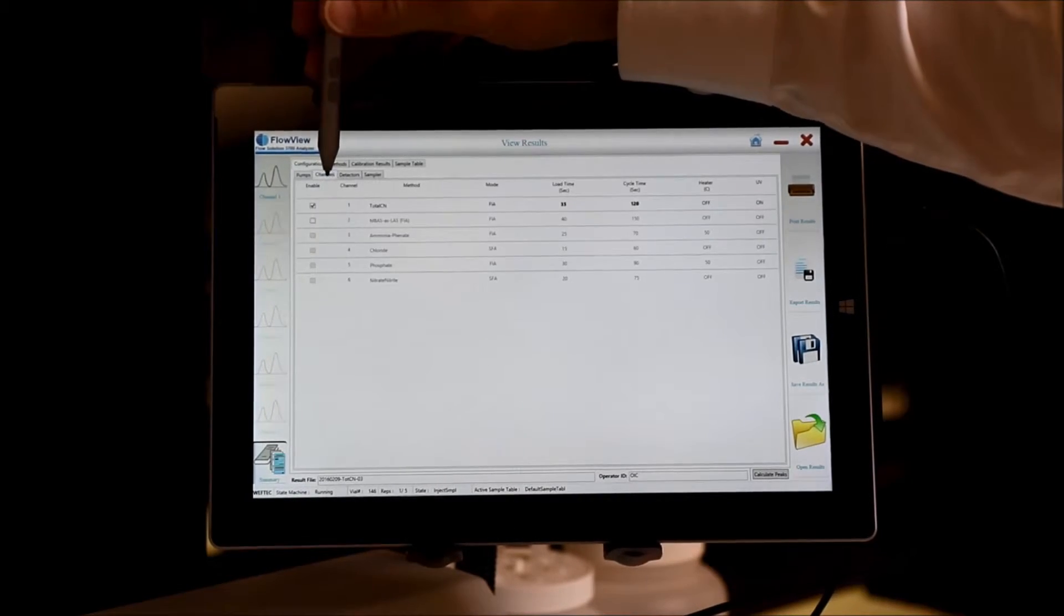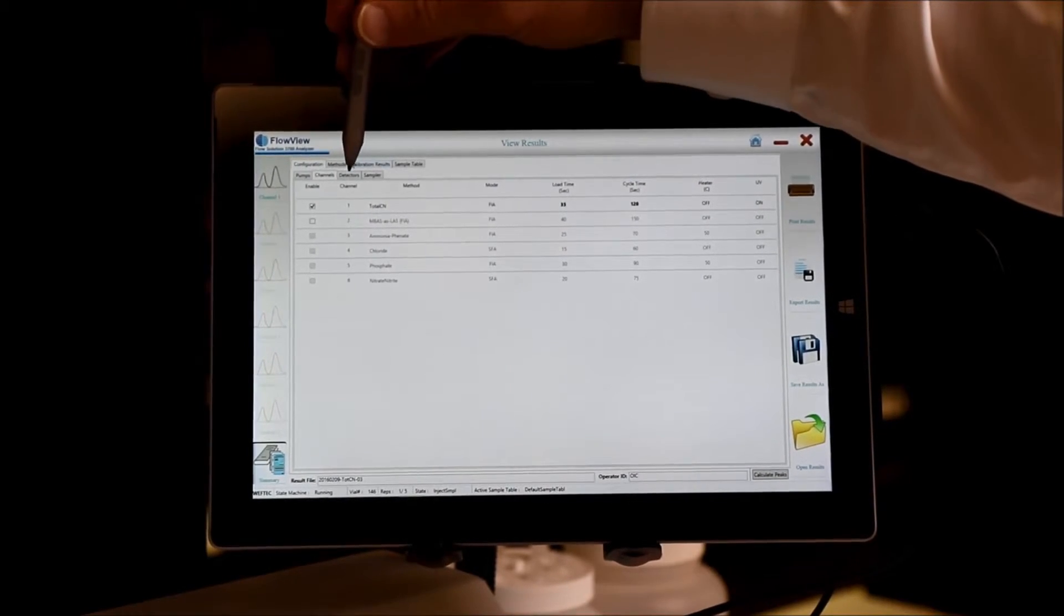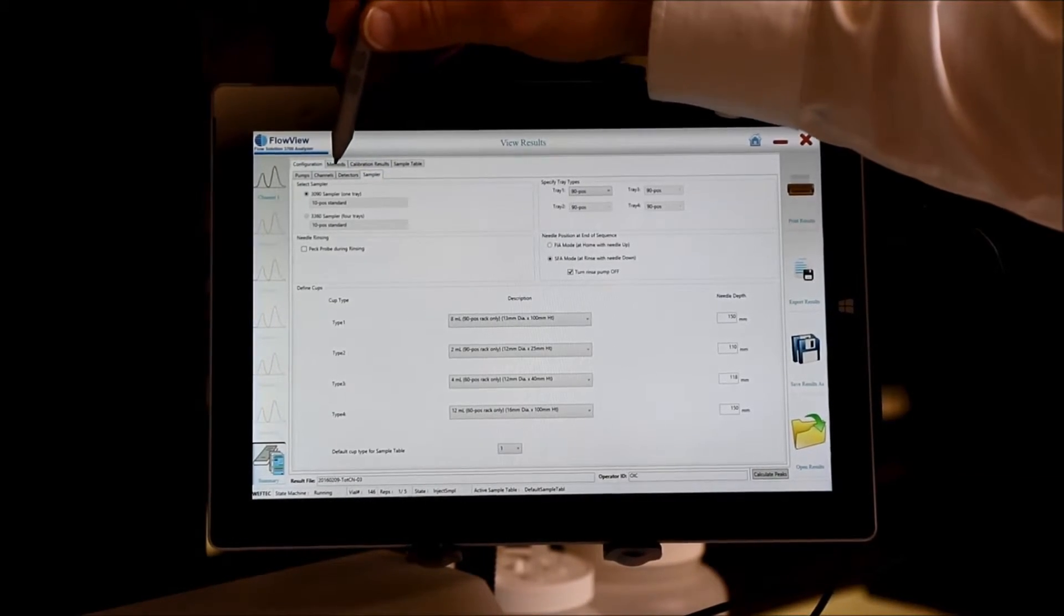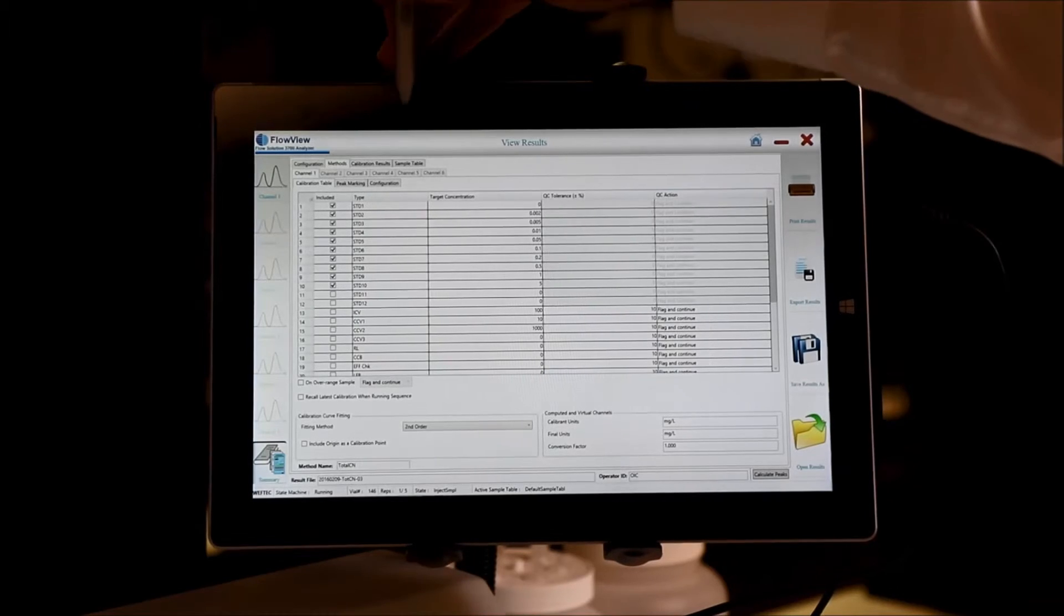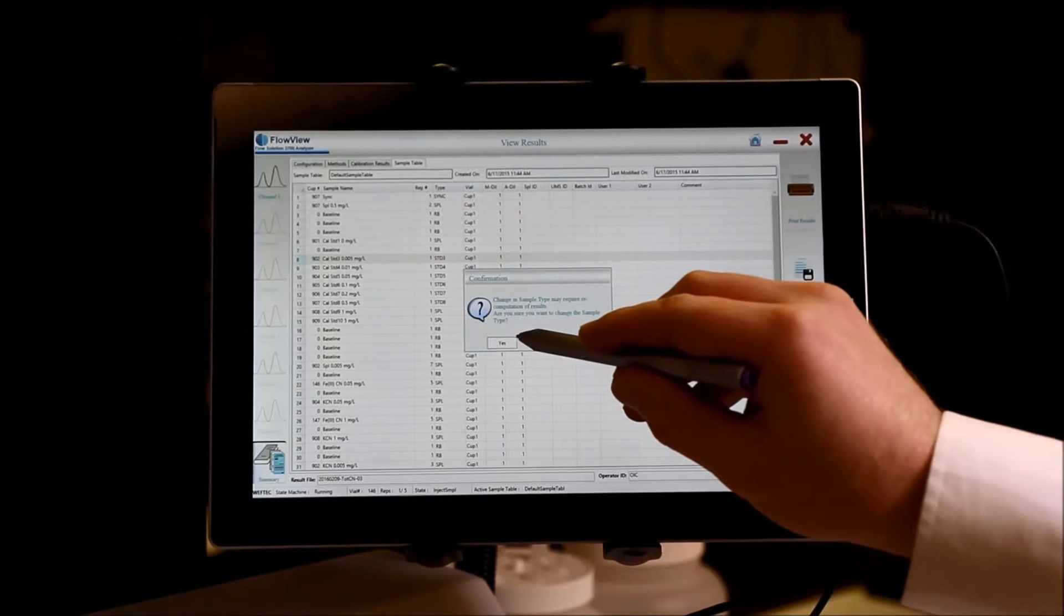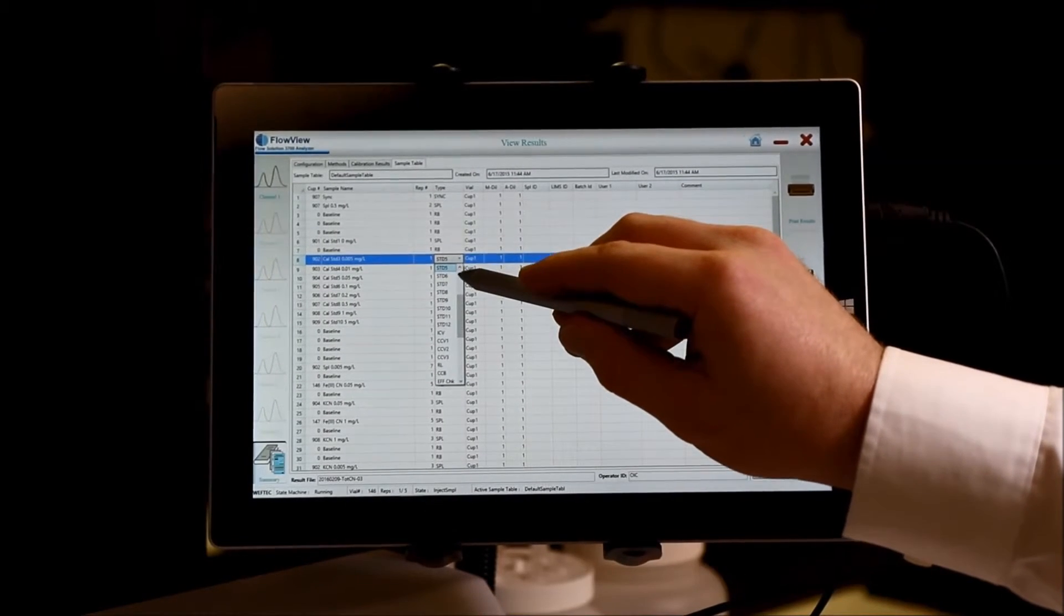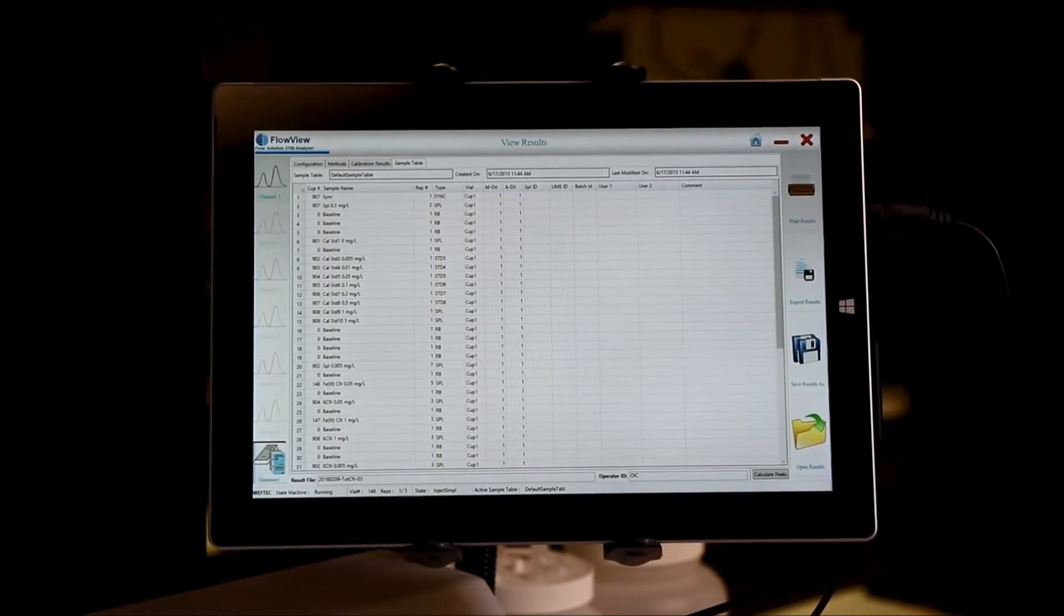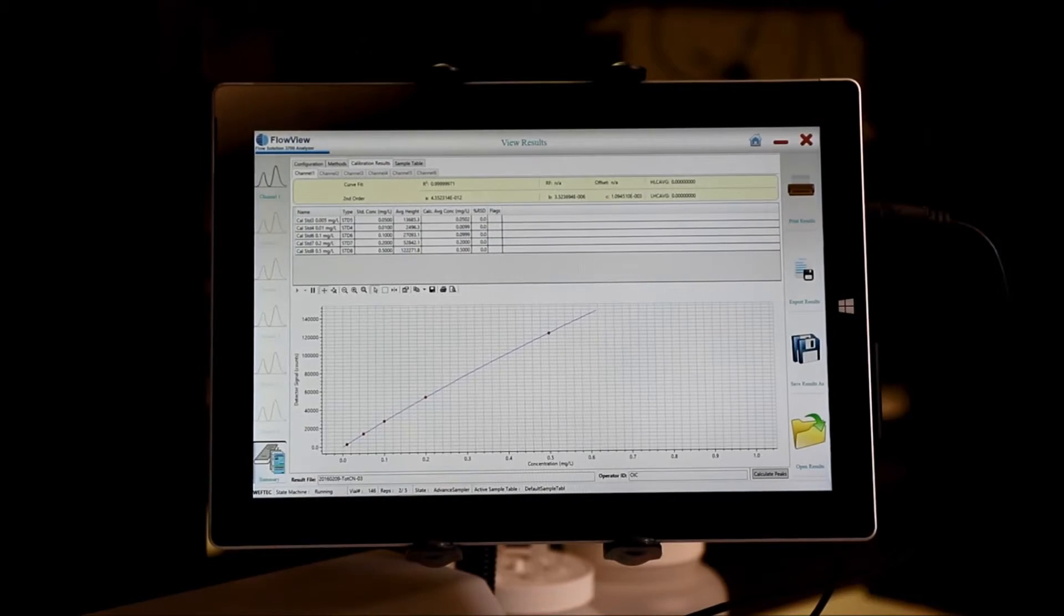All of the load time, cycle time, whether a heater was used, what the detector gain was, and even what the settings for the auto sampler were. We can also make modifications to the standard concentrations in case a mistake has been made, or from the sample table, choose to disregard samples and no longer use them in our calibration. All of these updates are applied immediately, allowing us to take a look at our calibration results and see how good the curve fit is.